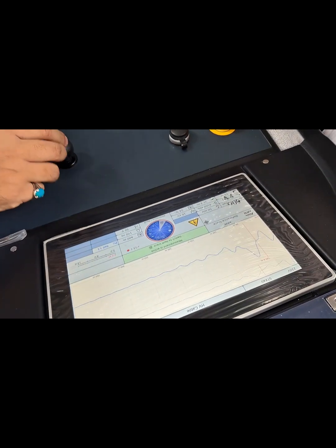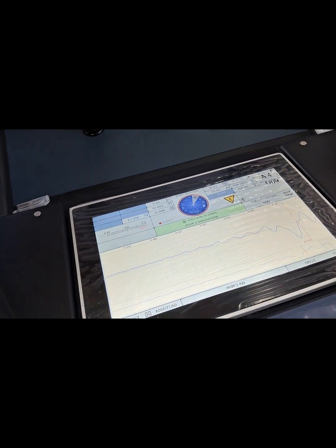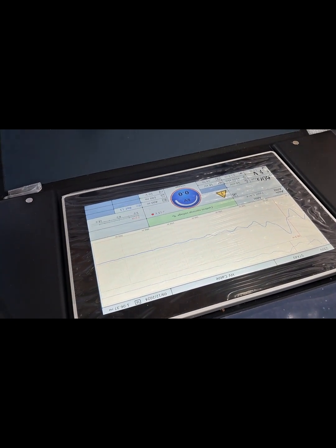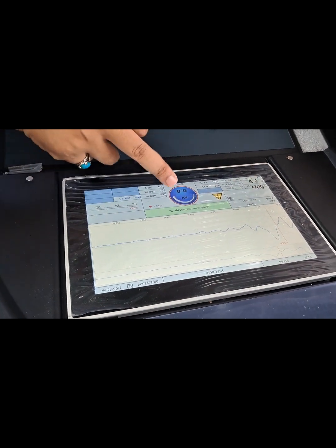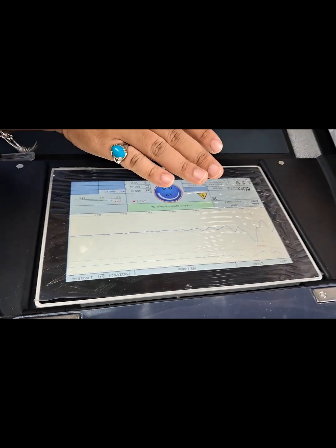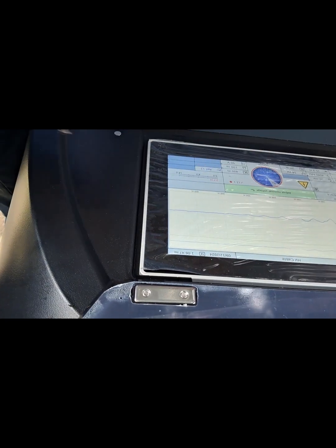Just enter. It will ask you. You have to take the fault graph now, to find where the exact fault distance is. It will ask how much voltage you have to inject. In TDR, you cannot do this much. You cannot get the fault graph. But in ARM, you can take TDR as well as fault graph.